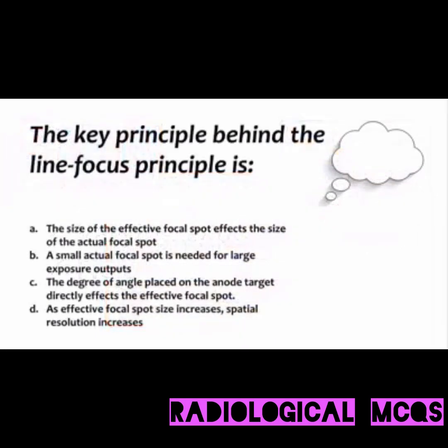Here's an example of a question you may see regarding the line focus principle. If you guess C, then you are correct. The fundamental principle behind the line focus principle is that the degree of angle placed on the anode target directly affects the effective focal spot size.